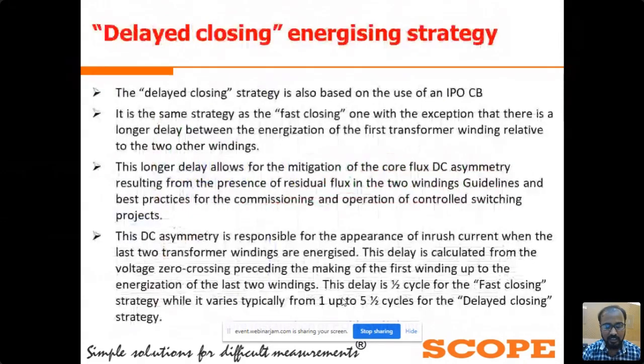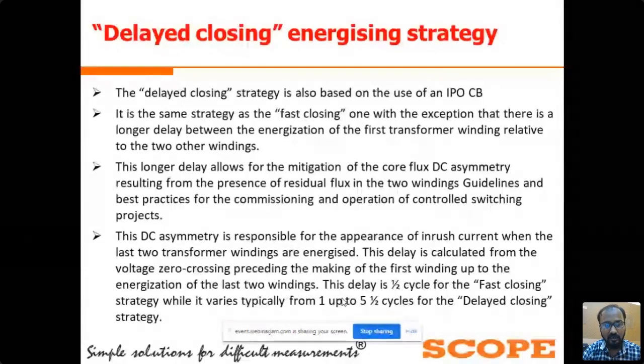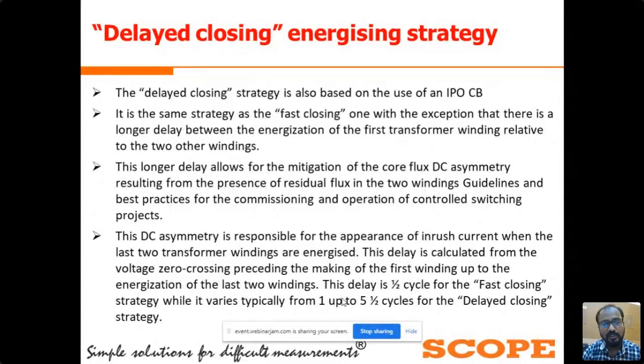With these two methods, we have another method also, called the actual calculation of residual flux in the power transformer. For that, we install bushing sensors at the tan delta point of the power transformer. This bushing sensor calculates the residual flux available in the power transformer by taking the reference of voltage at the time of de-energization. Having automatically calculated the residual flux, the CSD can decide the closing angles for the next energization of the power transformer.